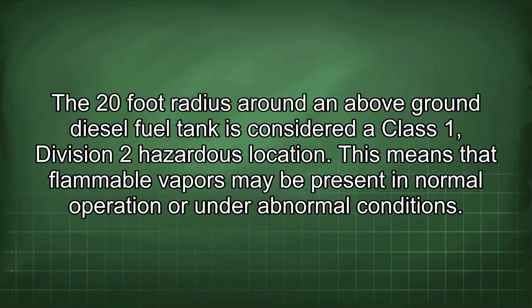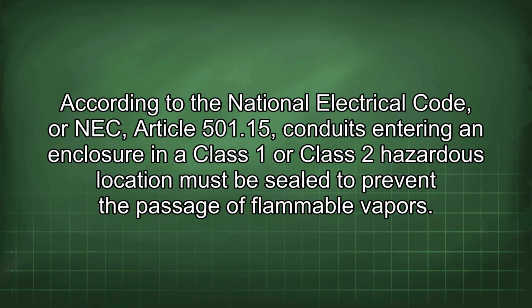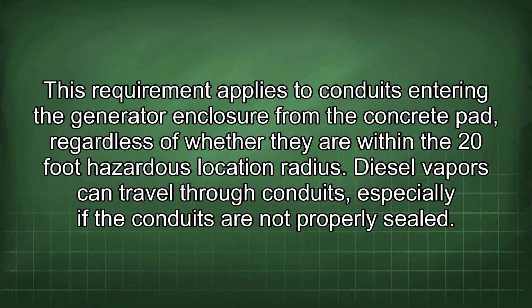This means that flammable vapors may be present in normal operation or under abnormal conditions. According to the National Electrical Code, or NEC, Article 501.15, conduits entering an enclosure in a Class 1 or Class 2 hazardous location must be sealed to prevent the passage of flammable vapors. This requirement applies to conduits entering the generator enclosure from the concrete pad, regardless of whether they are within the 20-foot hazardous location radius. Diesel vapors can travel through conduits, especially if the conduits are not properly sealed.